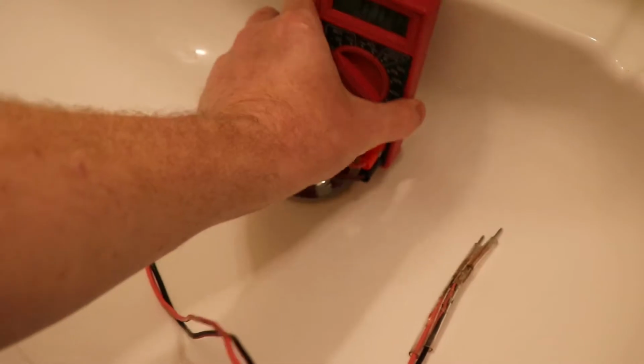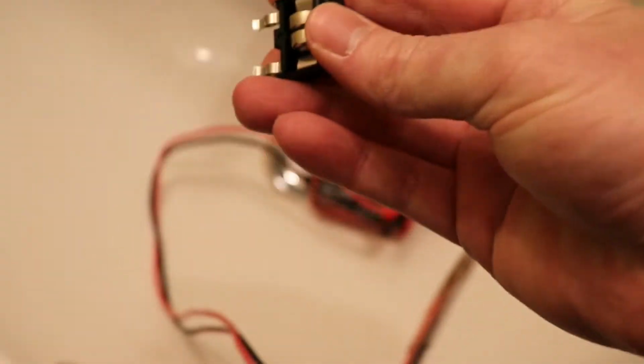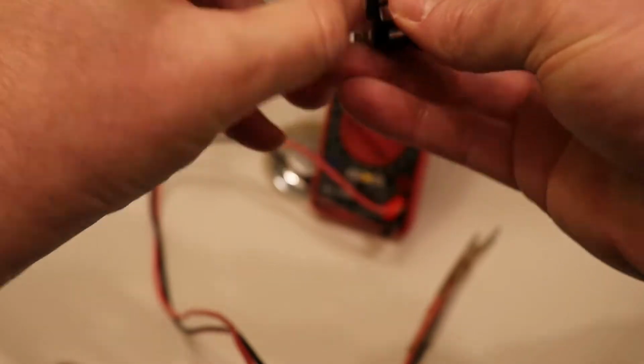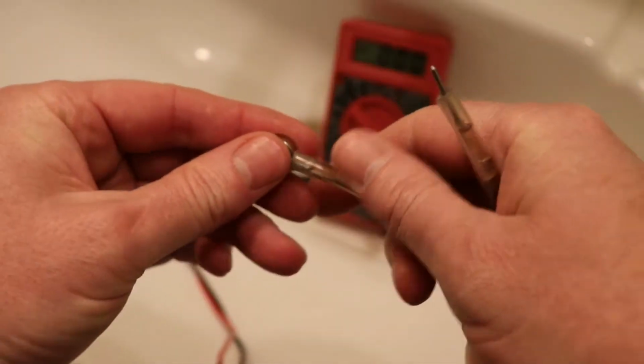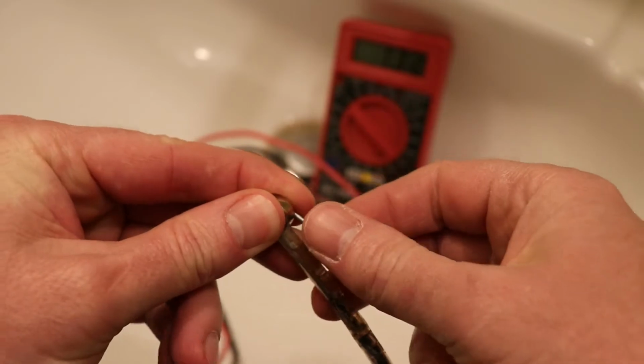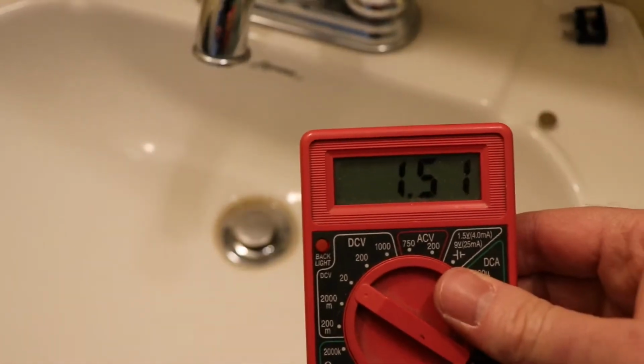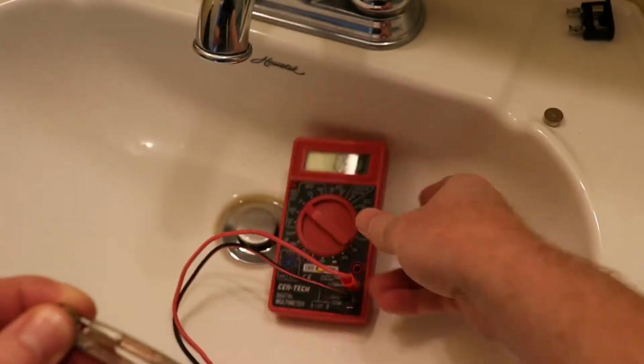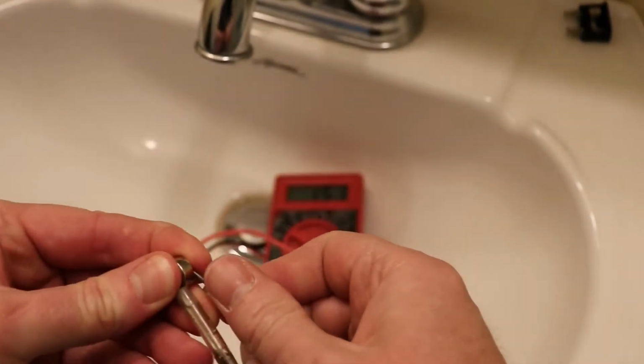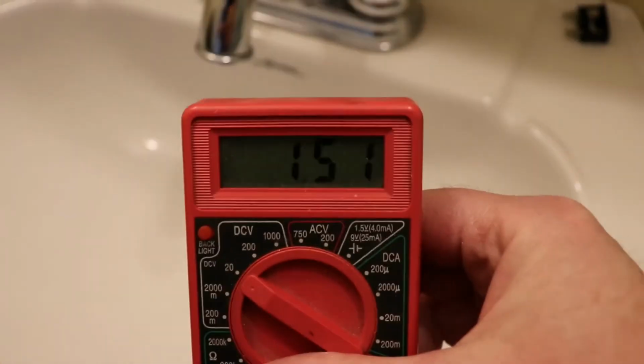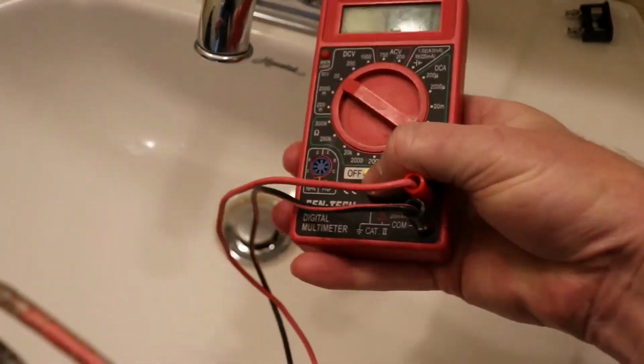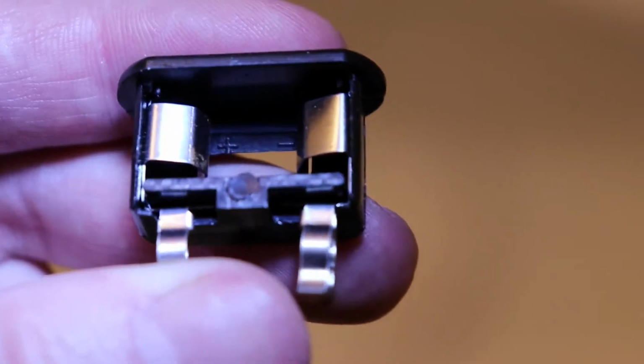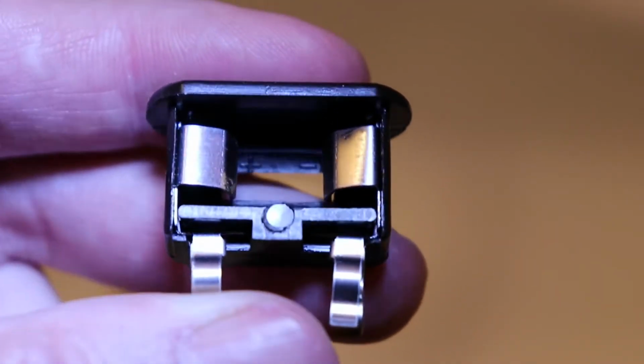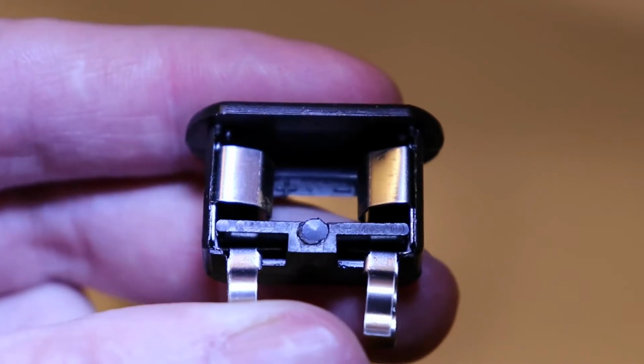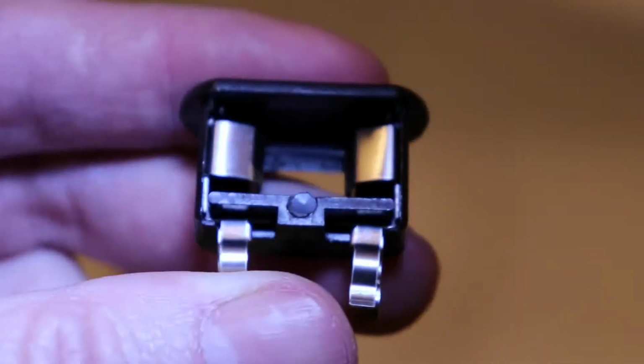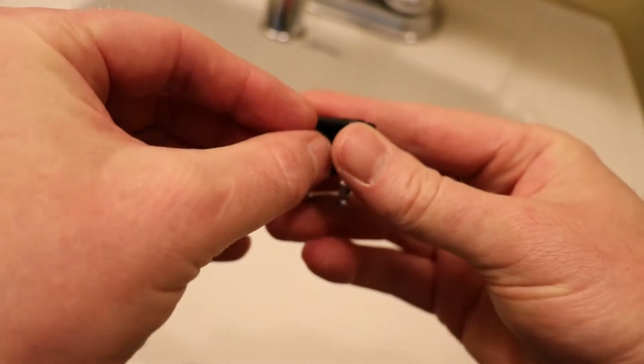Get a multimeter, pop these little batteries out, test the voltage on these. Should be a 1.5. So here's a good battery, 1.51. The other one's 1.51, so you know your batteries are good. You can see the plus and minus sign on this little battery cage here, so you know which polarity to put these in and don't get it backwards and fry your meter. So they go in like this.